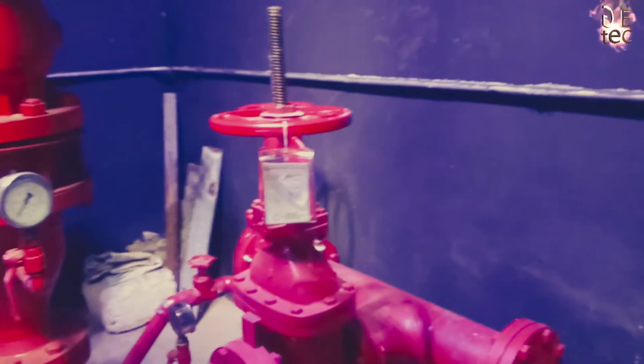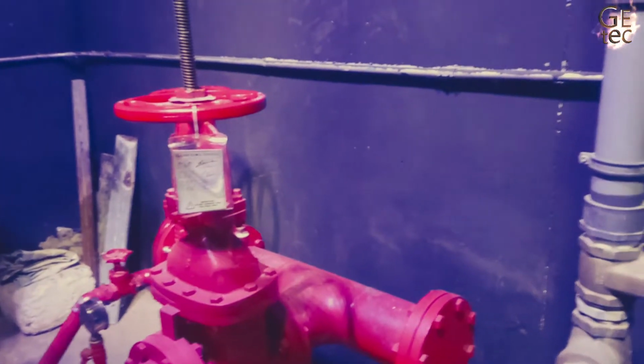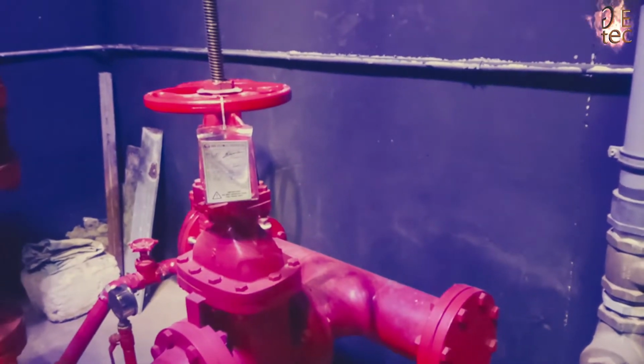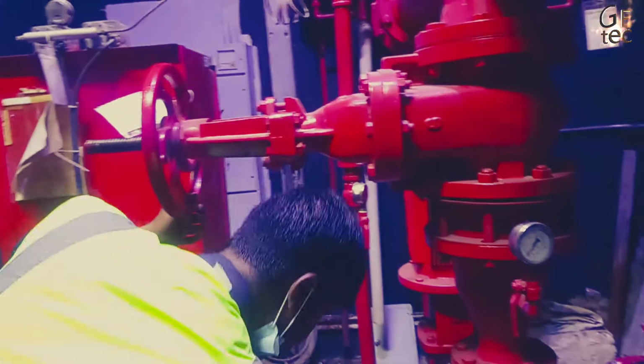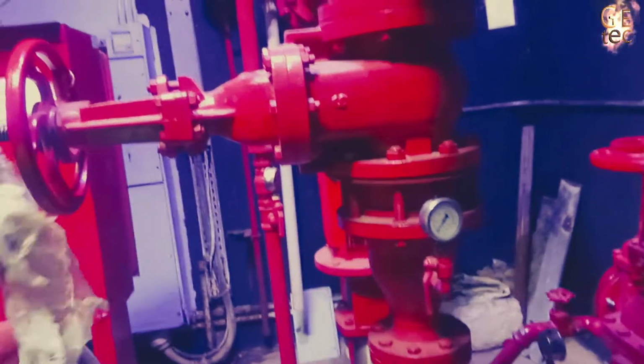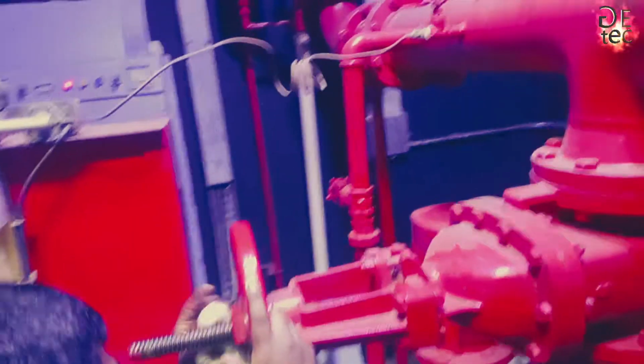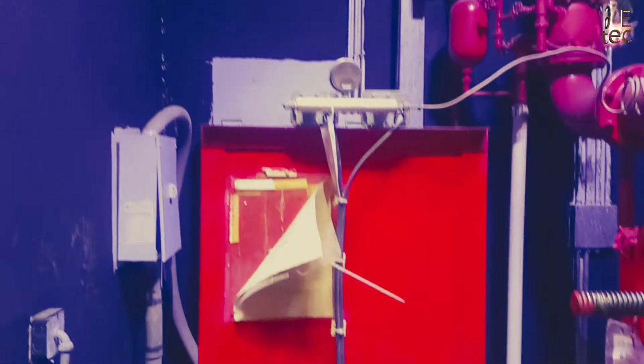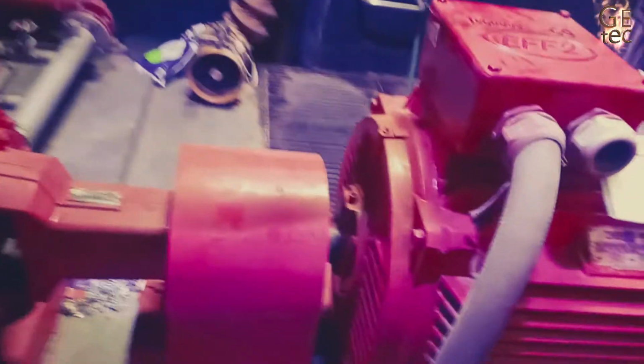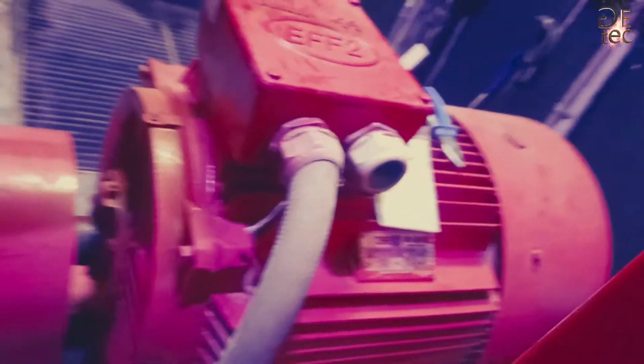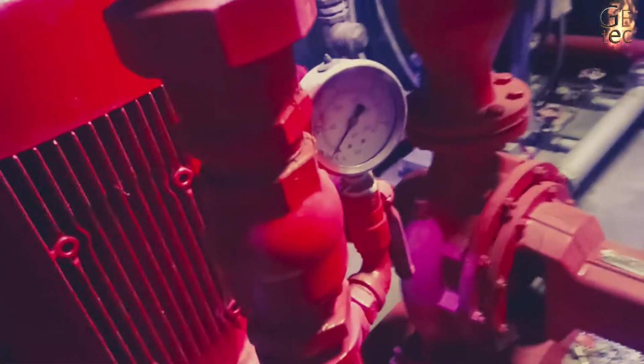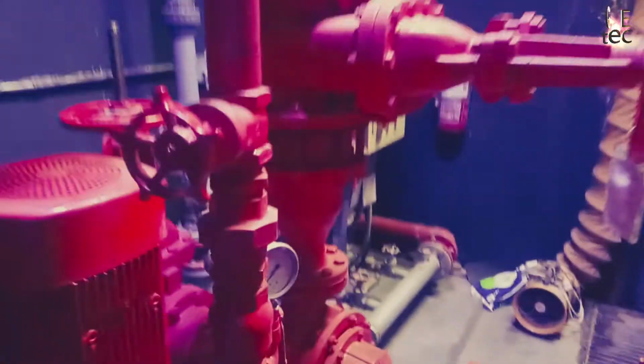A jockey pump, also known as a pressure maintenance pump, is a small apparatus that works together with a fire pump as part of a fire protection sprinkler system. It is designed to keep the pressure in the system elevated to a specific level when the system is not in use, so that the fire pump doesn't have to run all the time and the system doesn't go off randomly. It can also help prevent the system from damage when a fire happens and water rushes into the pipes. These devices consist of a three-part assembly. In many places, there are governmental guidelines and recommendations for installing these devices to make sure they work properly.